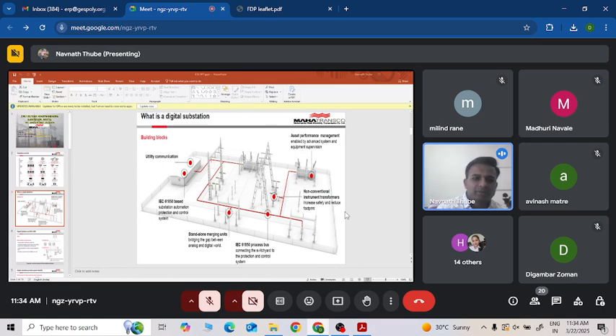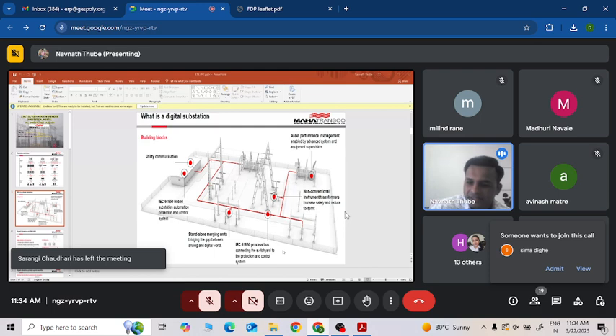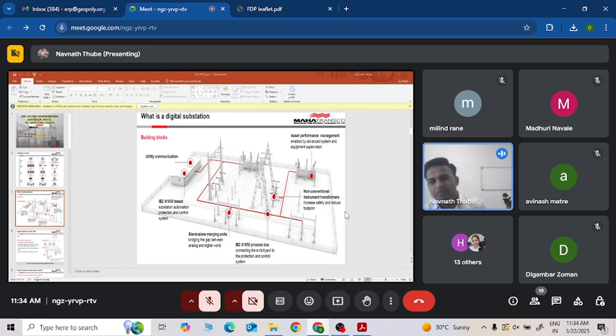The advantages of this digital substation: reliability and availability, safety and security, reduced lead time, reduced footprint, upgradability, very little maintenance, and flexibility. I just want to share this regarding safety and security. As all the copper cable gets replaced by fiber optic cable, there is very little chance of accidents in the switchyard area. This reduces the risk and increases the safety.